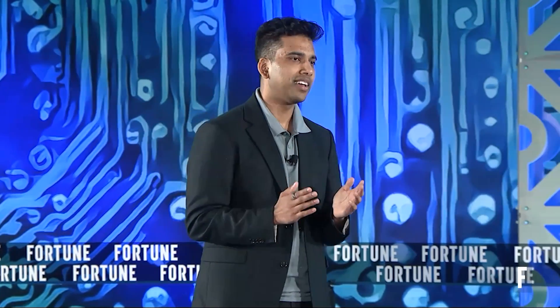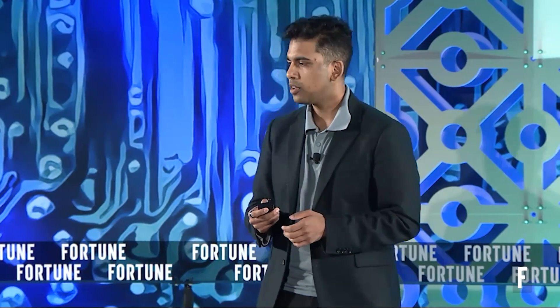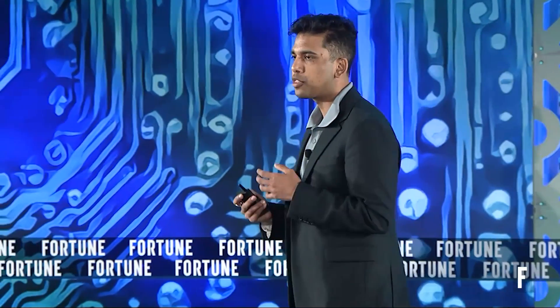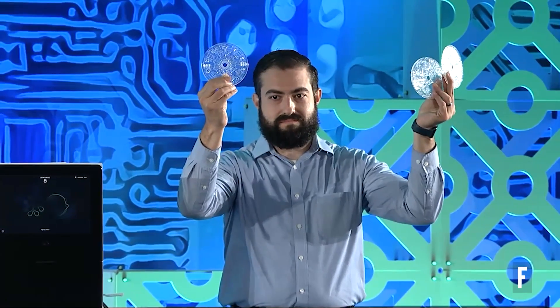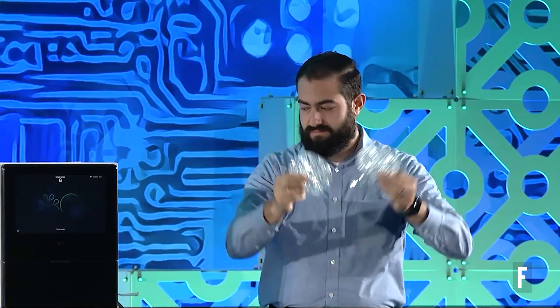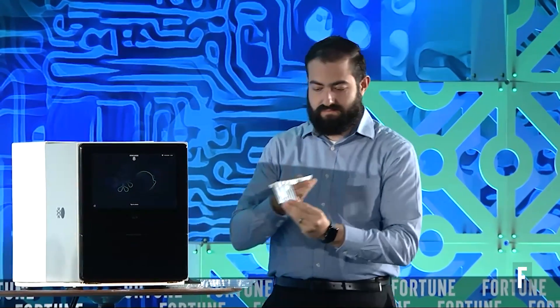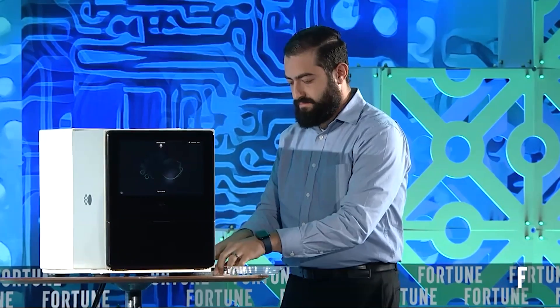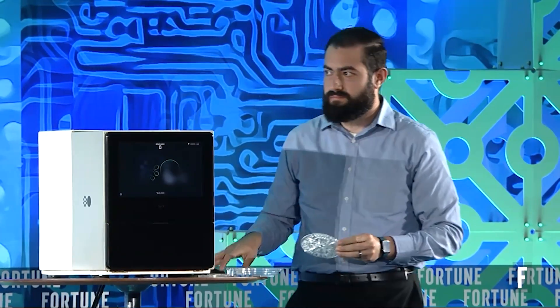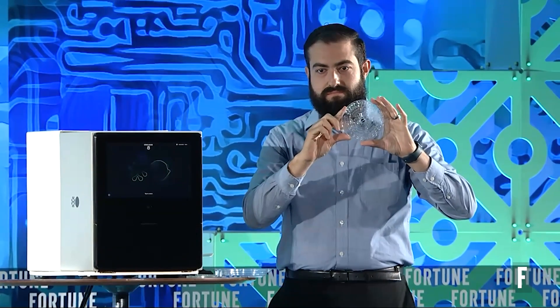You're probably wondering how this works, and we've got a few slides to go through today to show you. Inside that disk pack are three microfluidic disks. Each disk does a different modality of test, and within that support pack are reagents and tips. Within each disk are small lyophilized beads. Those beads contain all the reagents necessary to run these tests, and they're freeze-dried to eliminate the need for refrigeration or cold-chain shipping, seamlessly fitting into your workflow.